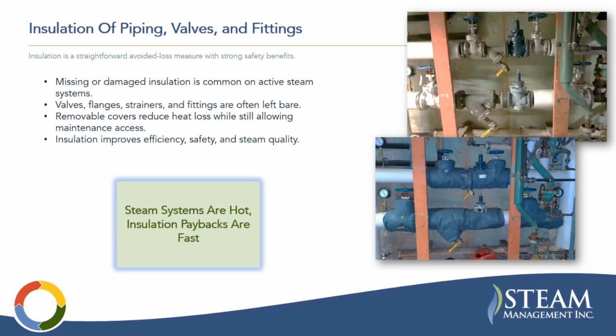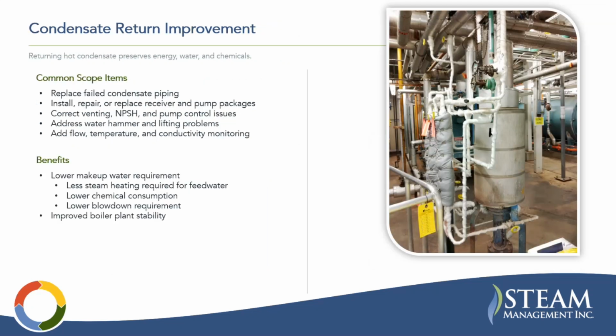Steam systems are hot compared to other utility systems, so insulation paybacks are fast. If you ever evaluate, like, a chilled water system, insulating a steam system is going to be a much faster payback than something like that. For example, condensate return improvement. Some common scope items here are replacing failed condensate piping, installing, repairing, or replacing receiver and pump packages, correcting venting, net positive suction head, and pump control issues, addressing water hammer and lifting problems, and adding flow, temperature, and conductivity monitoring.